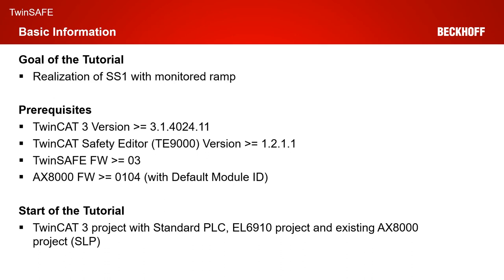The goal of today's tutorial is the realization of an SS1 functionality with a monitored ramp. At runtime we want to trigger SS1 and the downramp of the drive is monitored until it finishes within the STO state.